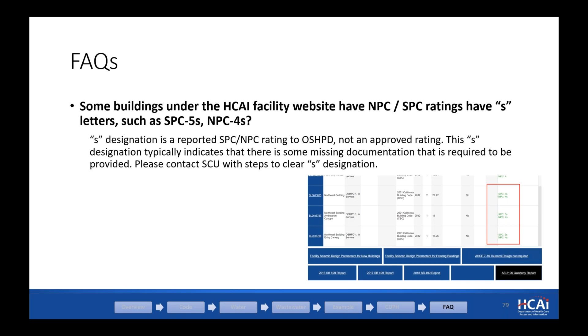One of the questions is, some of the buildings under the HCAI facility website have NPC or SPC ratings with an S letter, such as an SPC 5S or an NPC 4S. So what does that mean? S is a designation reported to OSHPD. This is a self-designated number. It's not an approved rating. This S designation typically indicates that there is some missing documentation that is required. So if you see this for your facility, please contact the Seismic Compliance Unit, and we can explain the further steps that are required to clear this designation. A lot of times S is relevant when it's under construction, but if your project has completed construction and still shows an S designation, that should be resolved.